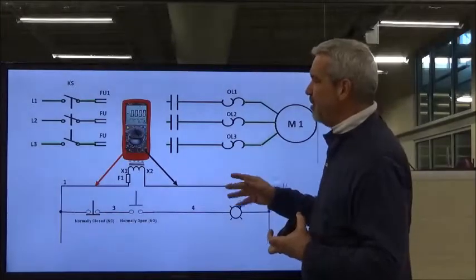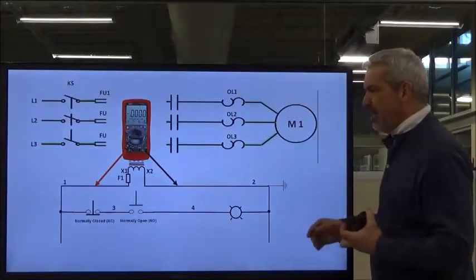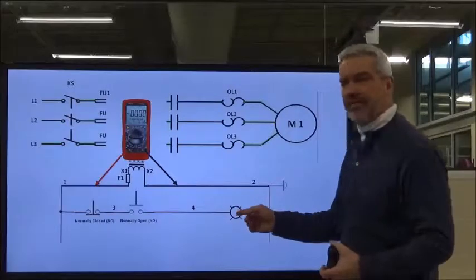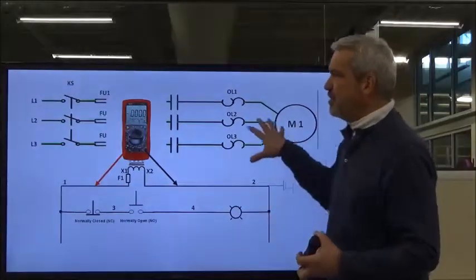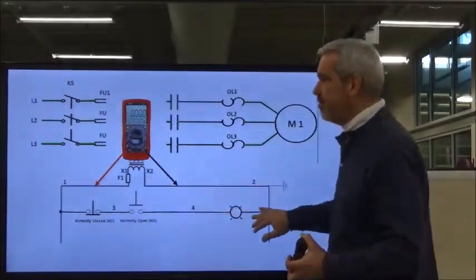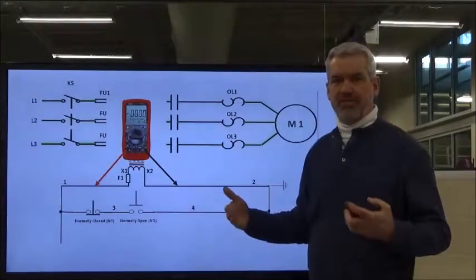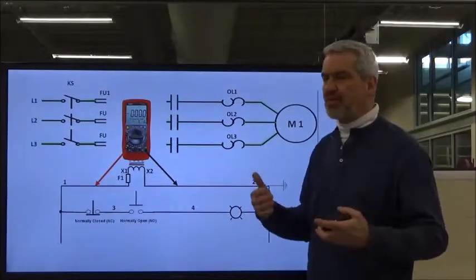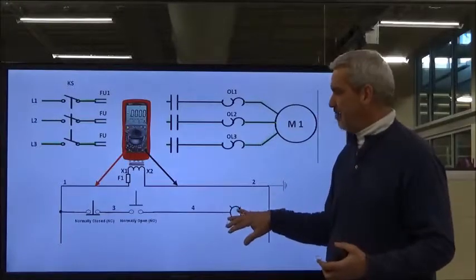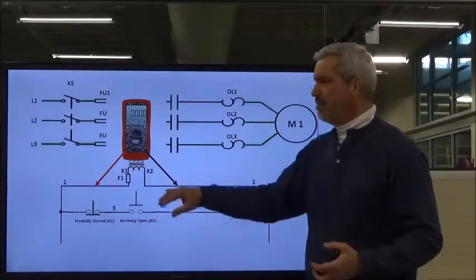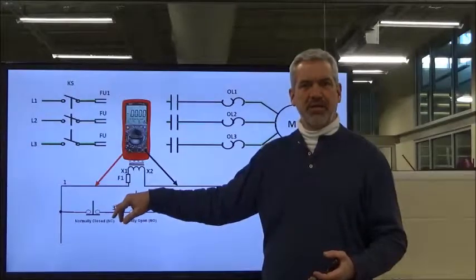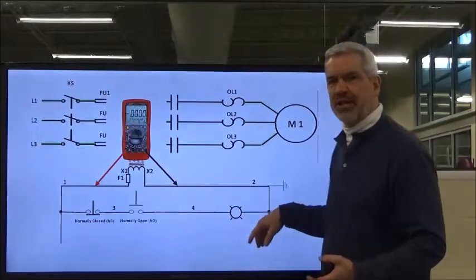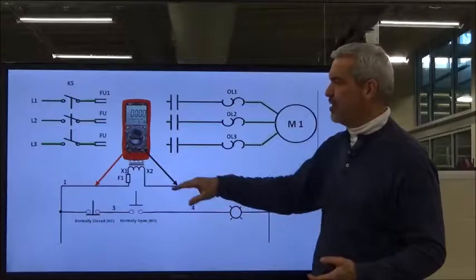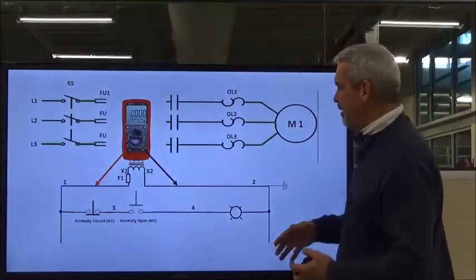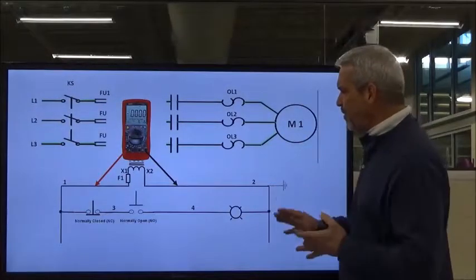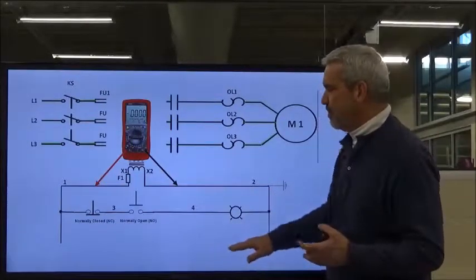Before I do that, before I put that meter and go to all that trouble, I'm going to use a little bit of common sense. I've got a light here, and usually machines have indicator lights, pilot lights and things throughout to give you some idea of if something's working, or if it's in automatic or manual, whatever. But if you've got some type of light or indicators going, you pretty much know the secondary is putting out control voltage, because that's where all your lighting and solenoids get their power from, the secondary of that transformer.